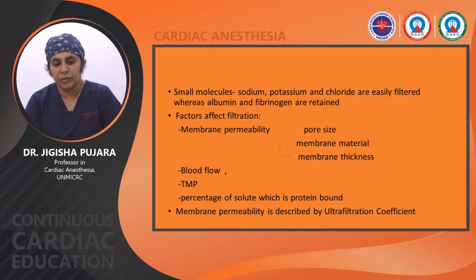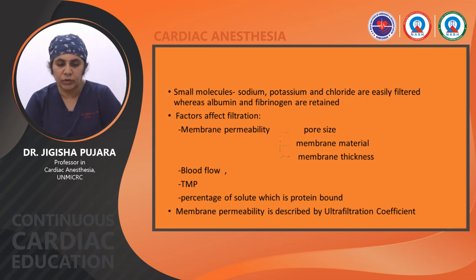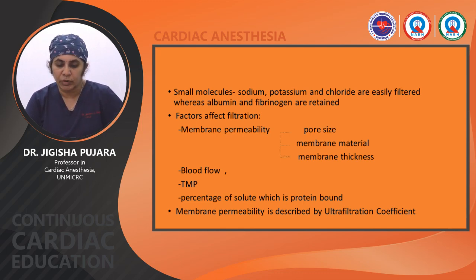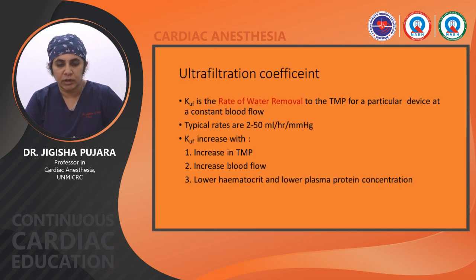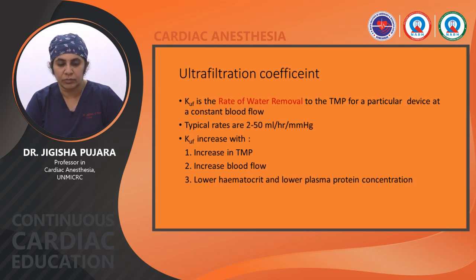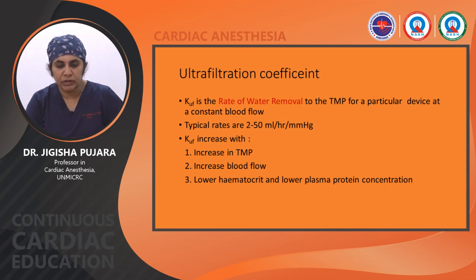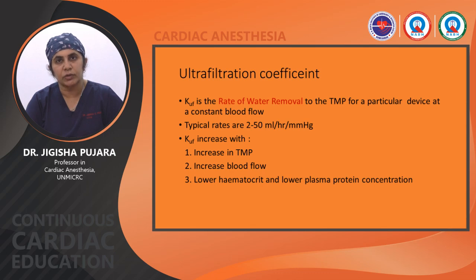Factors affecting filtration or membrane permeability include pore size, membrane material, and membrane thickness. It is also affected by blood flow, transmembrane pressure gradient, and percentage of the solute that is protein bound. Membrane permeability is described by the ultrafiltration coefficient — the rate of water removal relative to TMP for a particular device at constant blood flow. Typical rates are 2 to 50 mL per hour per mmHg. The ultrafiltration coefficient increases with increased TMP, increased blood flow, and lower hematocrit and lower plasma protein concentration.